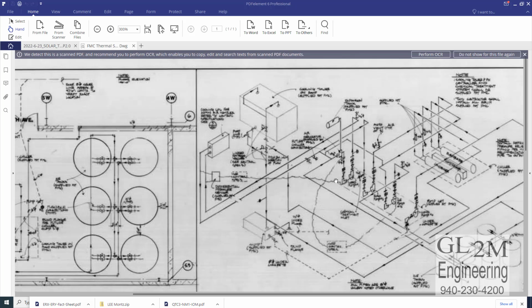Believe it or not, there are lots of chiller plants that are missing these. It's not a good design. In fact, it's dangerous. Without an air separator and an expansion tank, number one, it's hard for pumps to pump a mixture of water and air, so they're not very efficient if you don't have all the air out of the system.